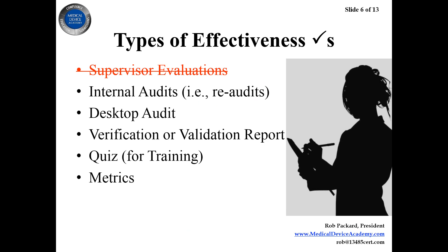The best method of all for effectiveness checks is something that has a metric — something measurable. That's why I like validation reports: they always have data and data analysis. Anytime you have a quality objective or a metric you can measure and graph, I can be convinced it's effective.